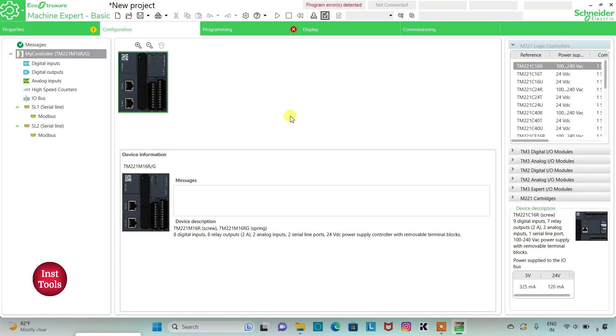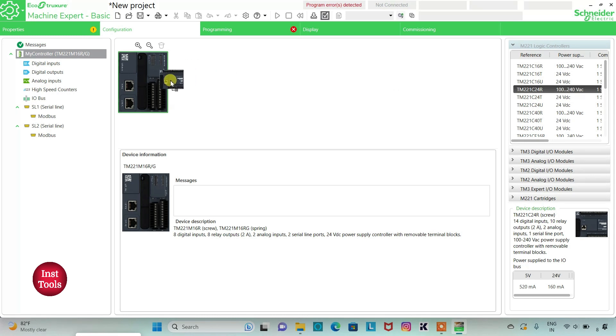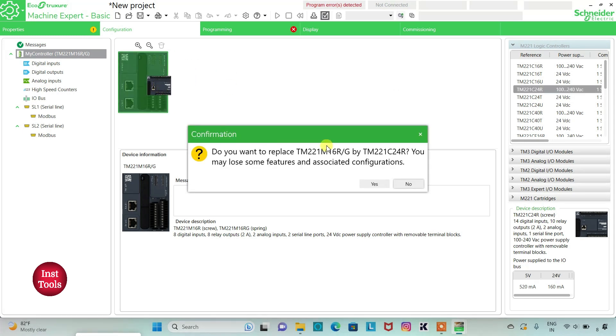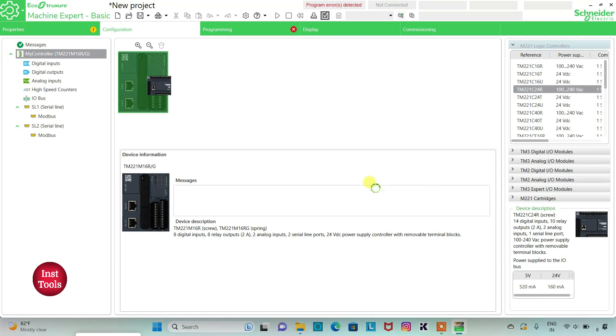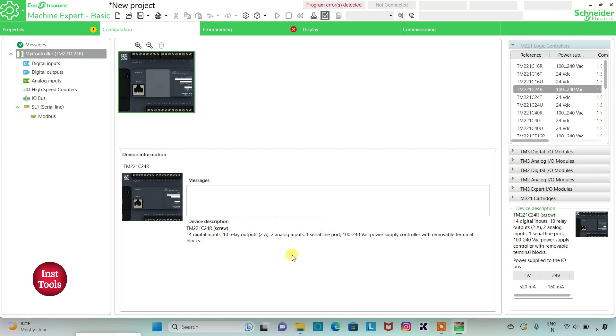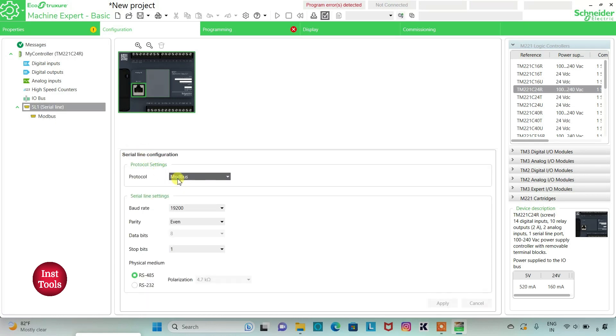Then I will go to the Configuration tab. Here is a list of logic controllers. I will be using TM221C24R — I will click on it and drag it here. Do you want to replace? You may lose some features and associated configuration. I will click on Yes. Here is the device description: it has 14 digital inputs, 10 relay outputs, 2 analog inputs, 1 serial line port, and a 100 to 240 volt AC power supply controller with removable terminal blocks. Then I can also go to Serial Line, where I will select the protocol as Modbus, and then click on Apply.